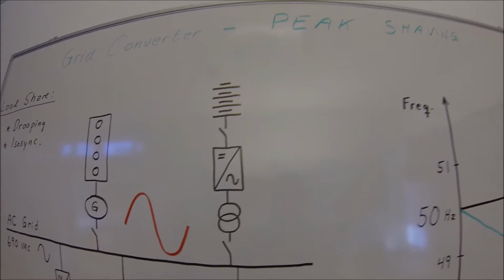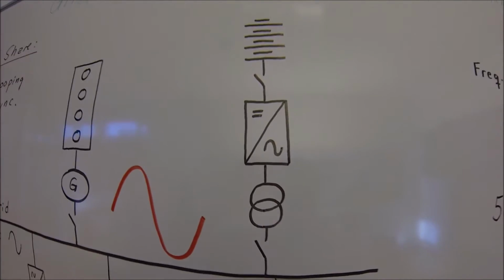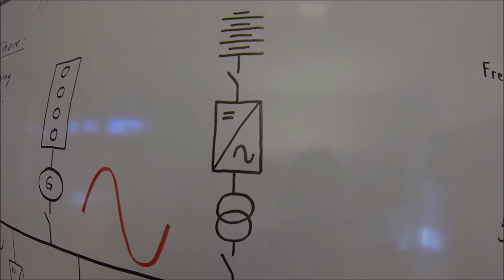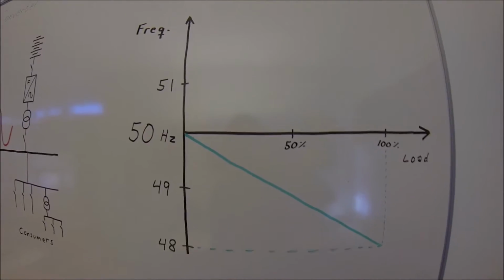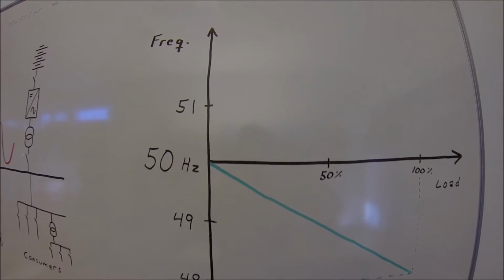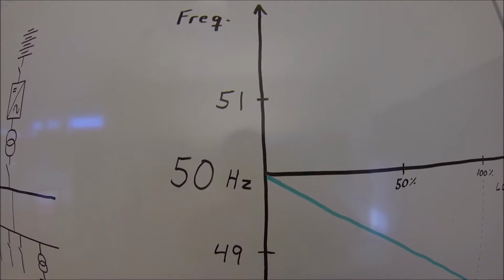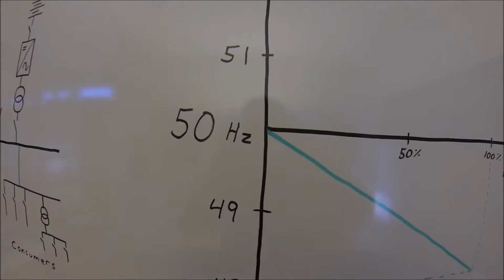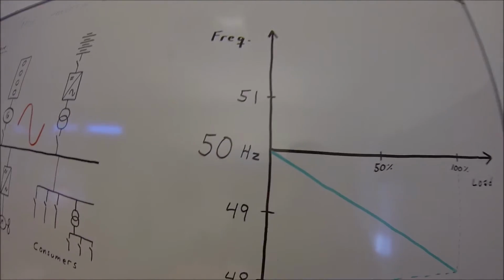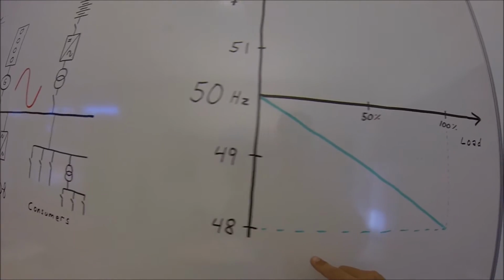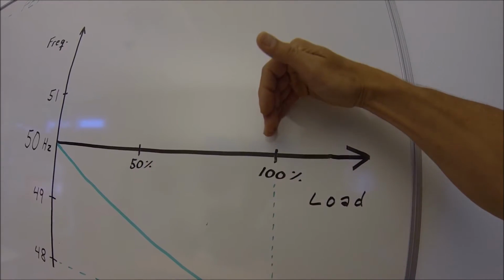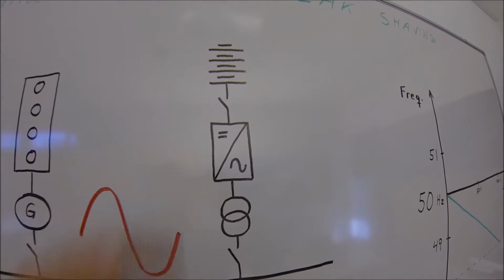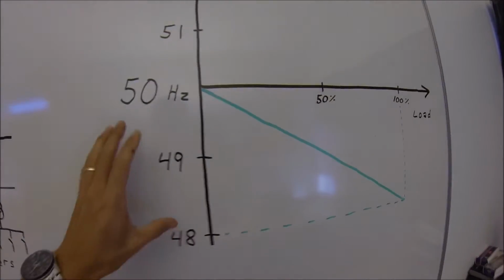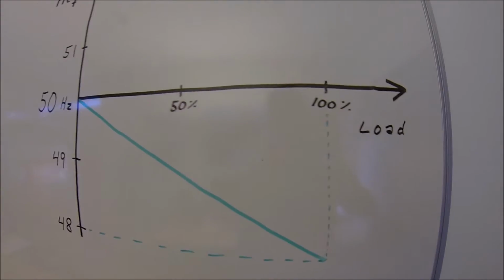Energy storage can do exactly the same thing. When we are running the grid converter in a drooping mode, we are doing exactly the same drooping function. We decide what the base frequency is. Let's say it's 50 hertz. We decide what the drooping is. Let's say it's 2 hertz. 2 hertz means that when you have achieved 100% of the nominal rating of this frequency converter, then you will have 2 hertz drop off.